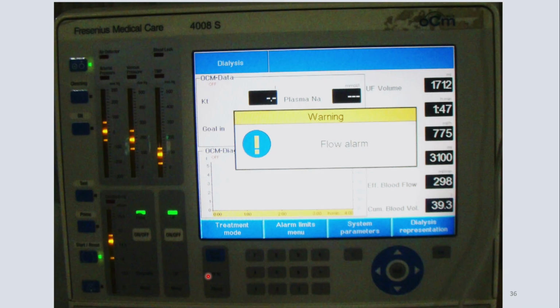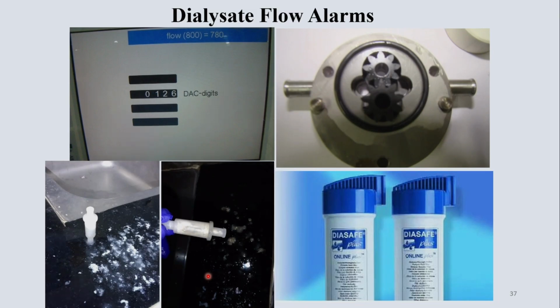Okay, so we did talk a little bit about preventive maintenance yesterday, about the various programs of disinfection that are available, including the importance of anti-scalant, and especially of decalcification, especially if you do not want to see this alarm frequently on the machine. So next slide, Vipul. The reason this arises could be because of this. What you can see here at the bottom left-hand corner is the degassing filter of the Fresenius machine, in a situation where somebody has not rinsed the machine and has switched it off with the conductivity in the operating range, and calcium carbonate precipitate has formed in the degassing filter, and that is going to result in that flow alarm. So the sites which can get blocked with a calcium carbonate precipitate are the Diasafe most commonly.